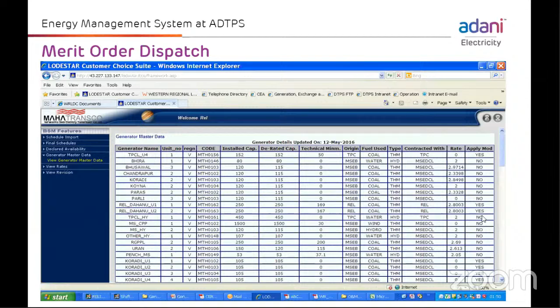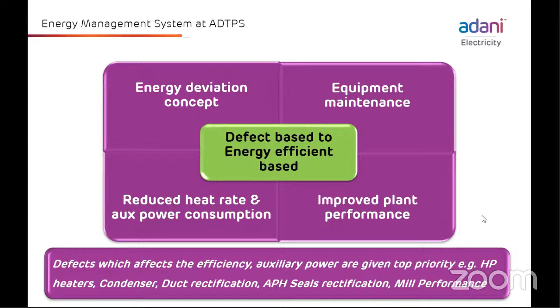Then we'll see what type of efficiency based maintenance. Now we have totally changed our philosophy from defect based to energy efficiency based, in which defects which affect the efficiency and auxiliary power consumption are given the topmost priority. For example, HP heaters, condenser, duct rectification, air preheater seal rectifications, mill performance, they are given the topmost priority whenever there is an opportunity to attend to them. For this identification, we have an energy deviation report, equipment maintenance, improved plant performance, and reduced heat rate and auxiliary power consumption.